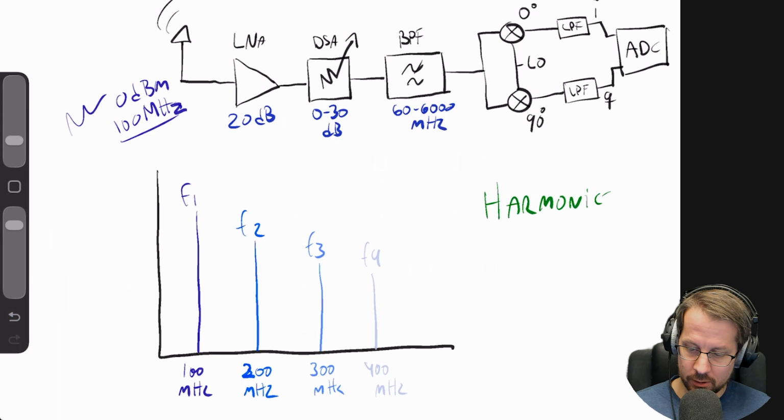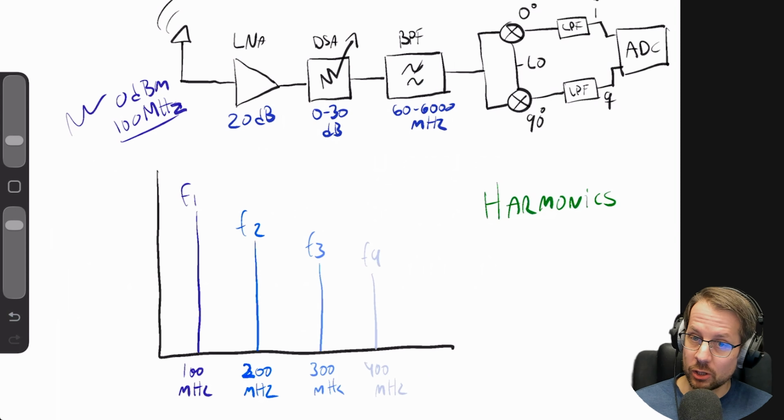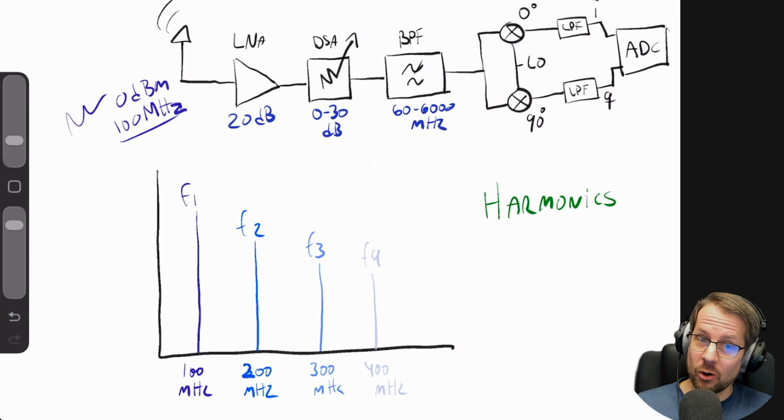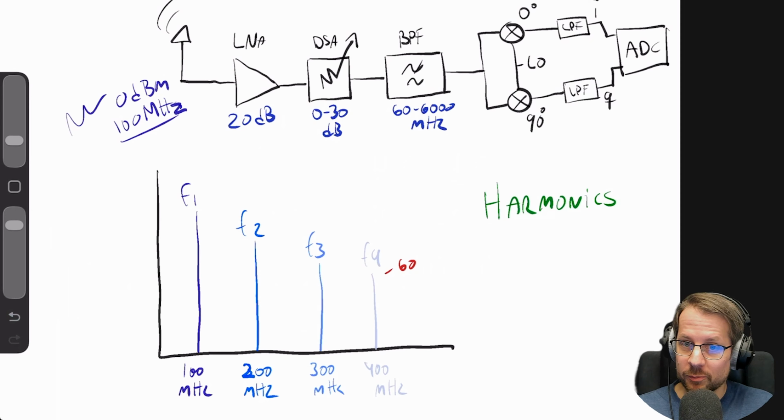Harmonics. So what is the easiest way for you to know if the harmonics is being generated inside your spectrum analyzer or from the outside? So let's say this value was -60, right? From 100 megahertz, you can use some typical free space path loss to know if you move further away, it will drop a couple of dBs, right?